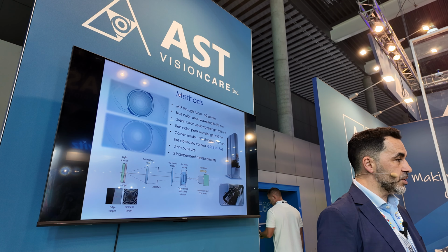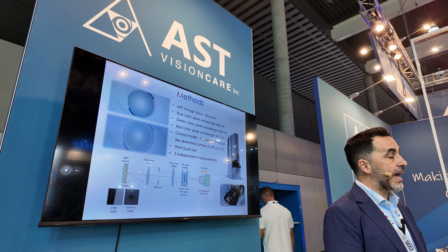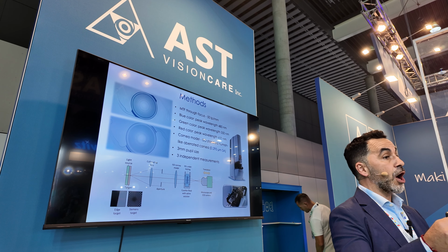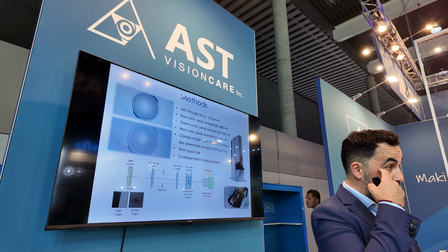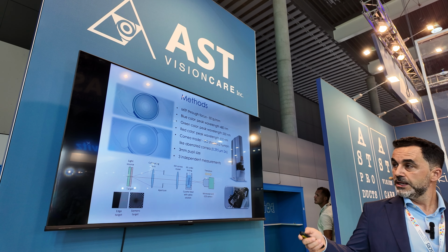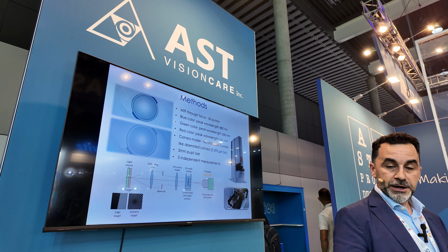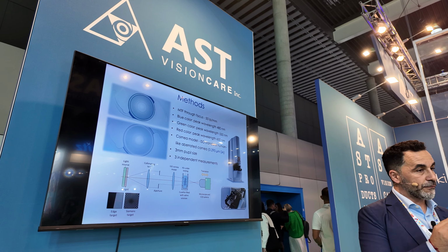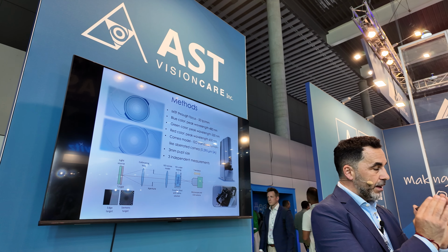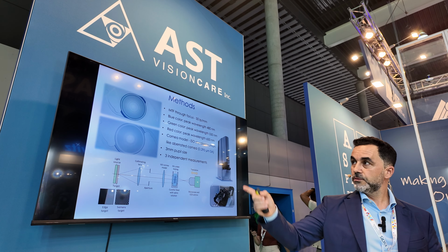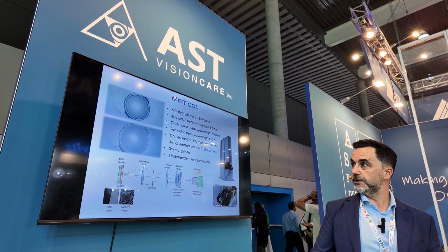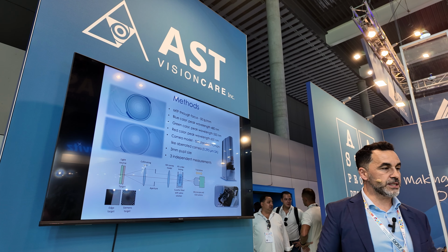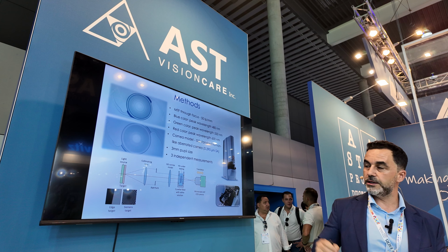So we know from quite extensive research that chromatic aberration in diffractive lenses is kind of compensated by the diffraction pattern. So we want to explore that with the Asqelio lenses. For that we measured the monofocal, trifocal, and EDOF IOLs of the Asqelio family. All of them have the same base biaspheric design, diffractive with a 15-ring diffractive pattern. And we explored wavelengths from 480 nanometers to 650 nanometers for the red color.